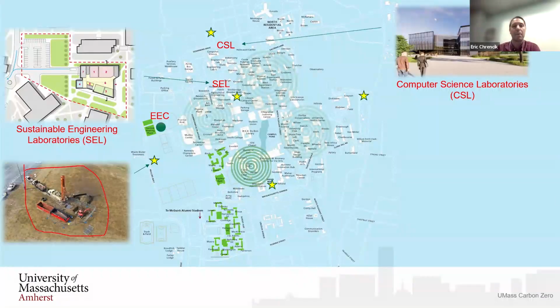And it just so happened up by the North Chiller plant, they had two buildings, one under construction and one renovation, and they were going to use standalone individual ground source heat exchanger systems. So they had their heat pumps involved, they had their ground source heat exchangers. Then as we were working on ours, the idea came up: okay, we have the North Chiller plant, we have some real estate there. There's a parking lot due north here, right above that CSL language, where they said it's a flat parking lot. We know the ground properties. We did a test bore right there. We can get about what was it, Bill, 100 or 120 in there, something like that? Yeah. So we said we can get 120 in there or so.